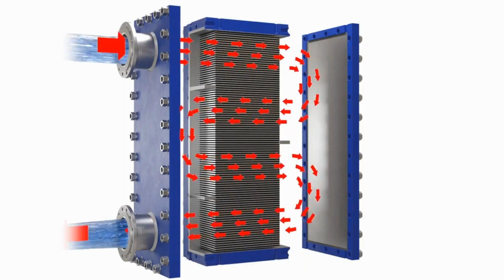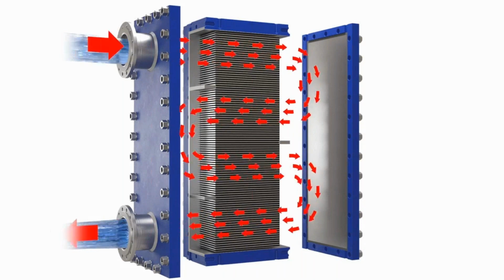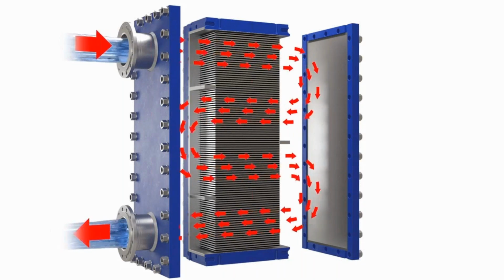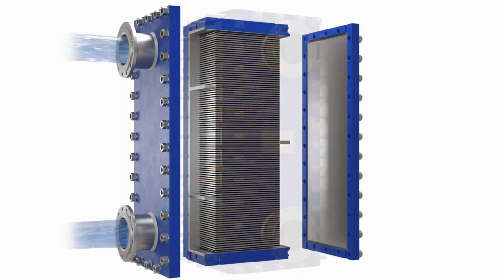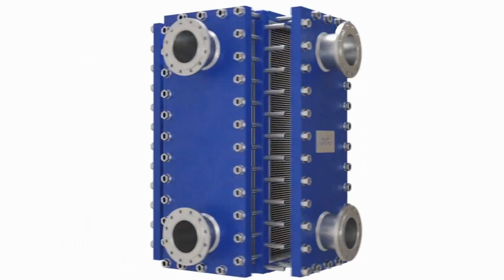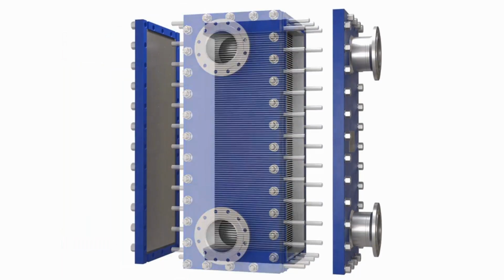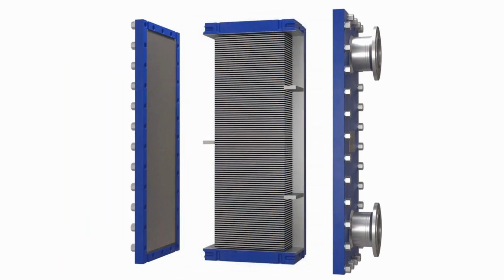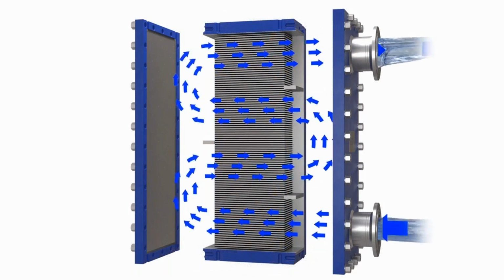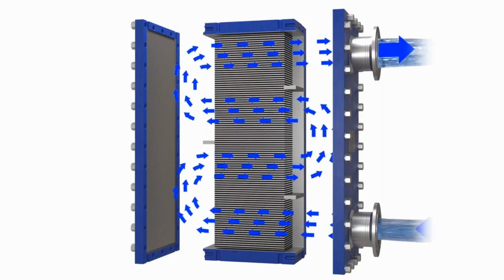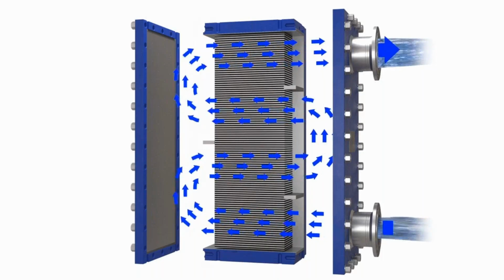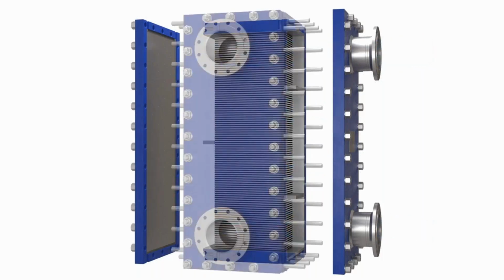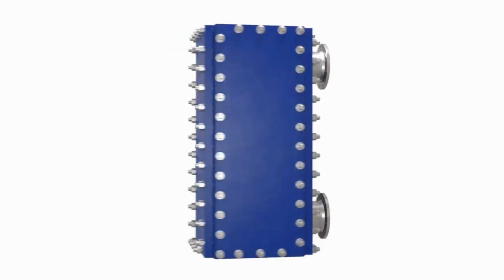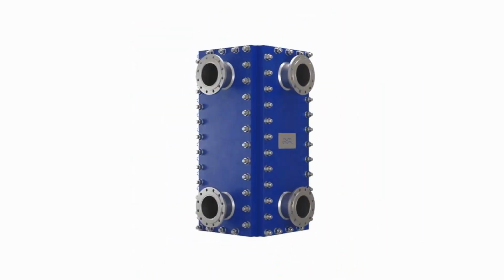As you can see, there's quite short plates on this unit, so to get the thermal length, we use multi-pass. And again, on the cold side. And the baffles shown here, we can move them to give different pass arrangements on each side of the exchanger. And this allows us to optimize the unit for different flow rates on each side.